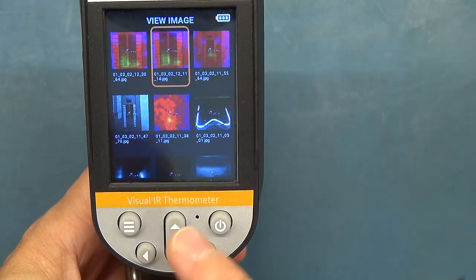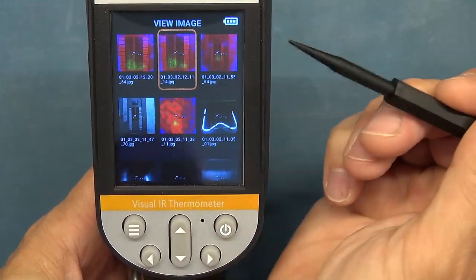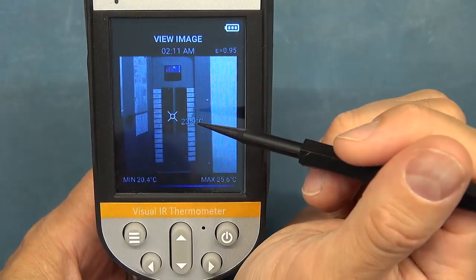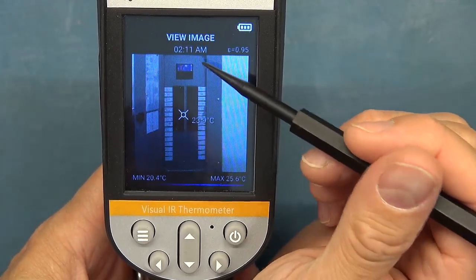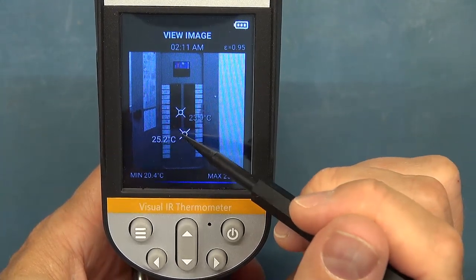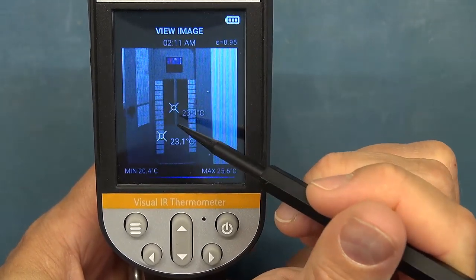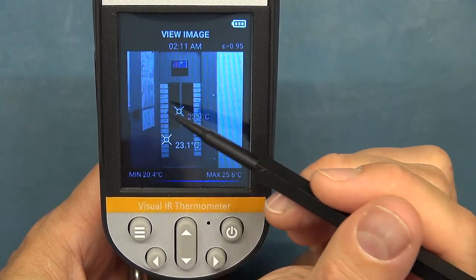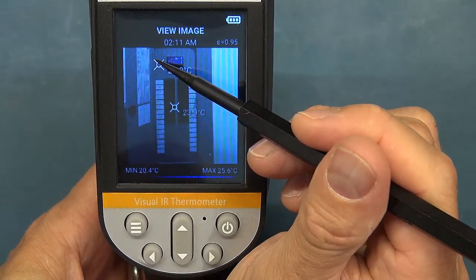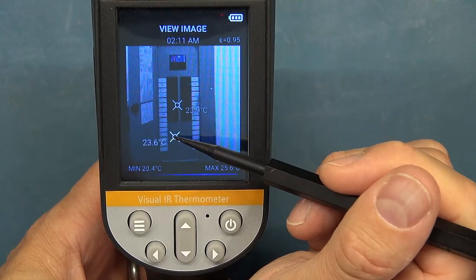You've got a delete setting and an option to select whether you want bitmap or JPEG — the bitmap might be a bit better. You can reset the camera. There's also a color palette selection menu. In certain situations, having a lot of color may not be useful — a black and white or monochrome palette may give better contrast when trying to see a subtle temperature change. Depending on your application, changing the color palette can be a preference or a practical choice.